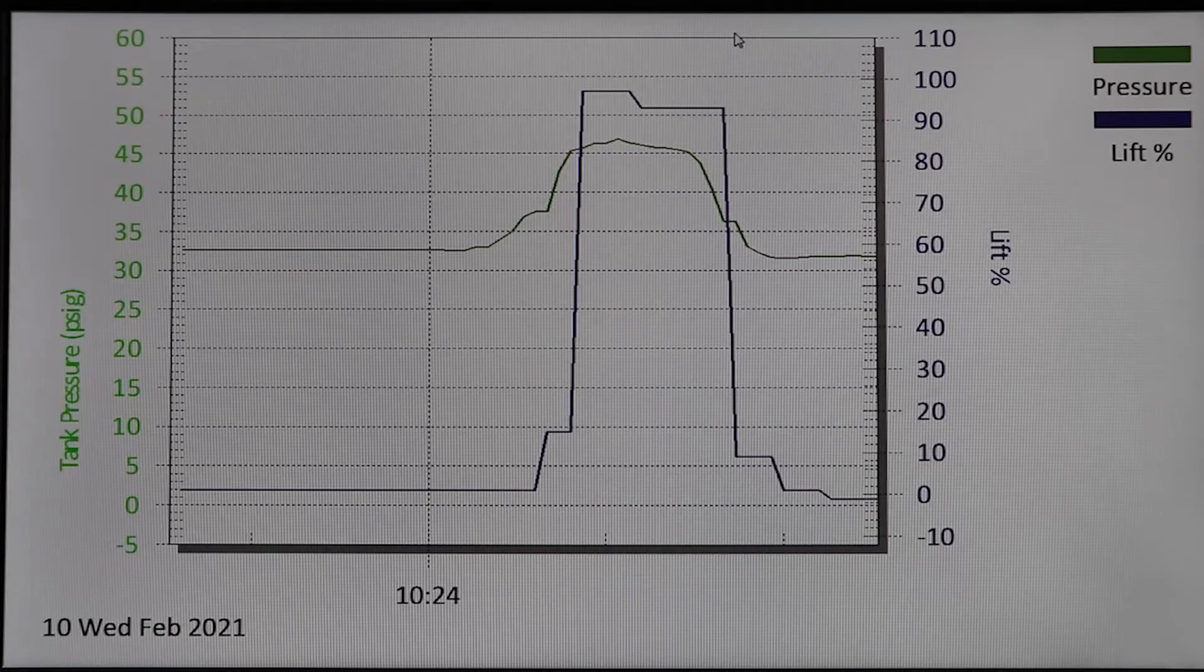In this example, you saw a relief valve that has opened and closed cleanly with very little simmering and no chattering, which is ideal for pressure relief valve operation.